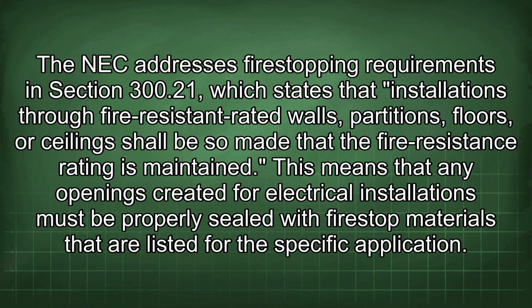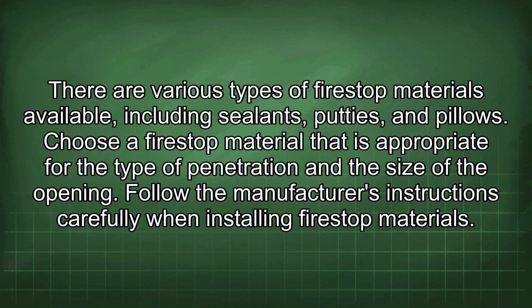of the building. The NEC addresses fire stopping requirements in section 300.21, which states that installations through fire-resistant rated walls, partitions, floors, or ceilings shall be so made that the fire resistance rating is maintained. This means that any openings created for electrical installations must be properly sealed with fire-stop materials that are listed for the specific application. There are various types of fire-stop materials available, including sealants, putties, and pillows. Choose a fire-stop material that is appropriate for the type of penetration and the size of the opening. Follow the manufacturer's instructions carefully when installing fire-stop materials.